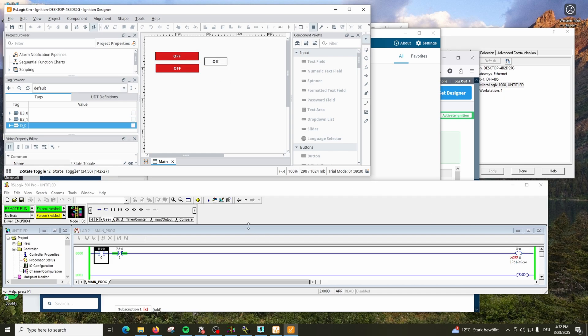This is how you can now make some logic, practice exercises which I'm doing with the real PLC - you can try with the simulated PLC. One important thing: don't activate the inputs - use B, not I. You don't activate the inputs directly from the PLC; you might receive a write error. Work on the bits and the output. You can take O for output, but for SCADA buttons don't use I for inputs. Feel free to try that and let me know if it works for you. Good luck for the rest of the course. Thank you for watching, see you in the next video.